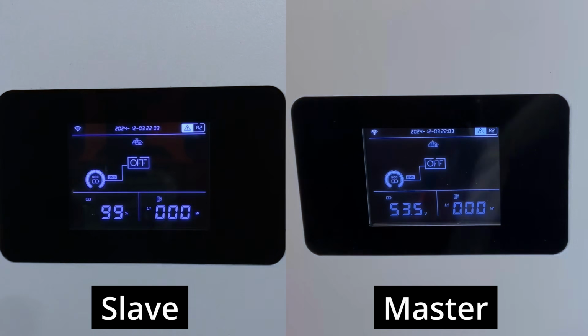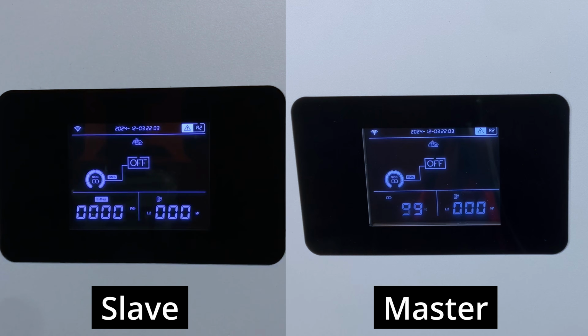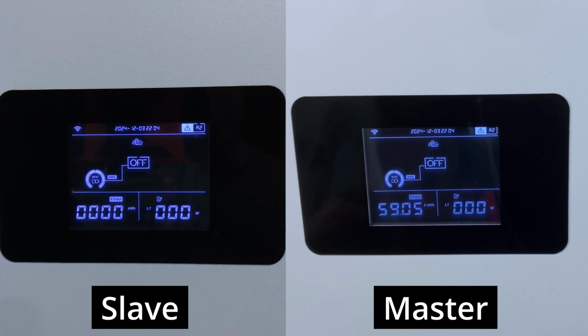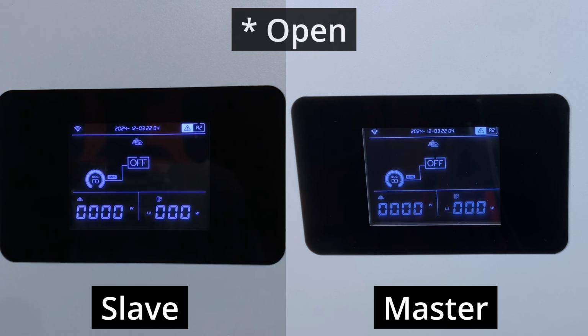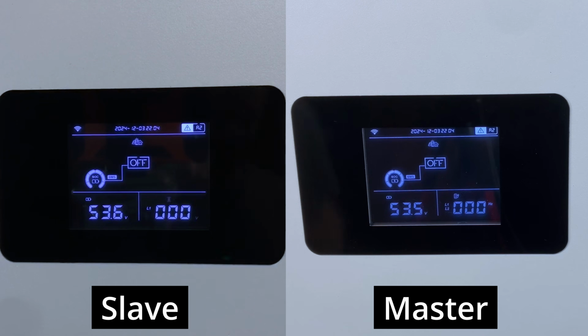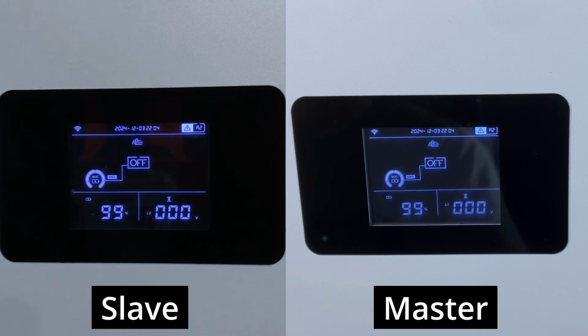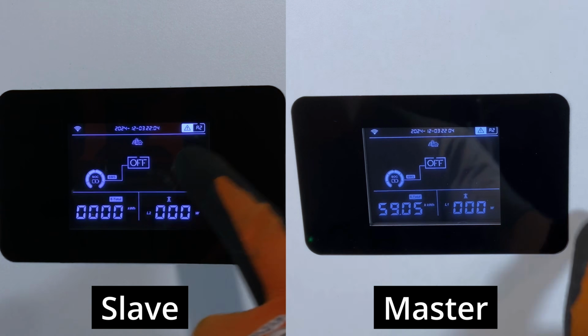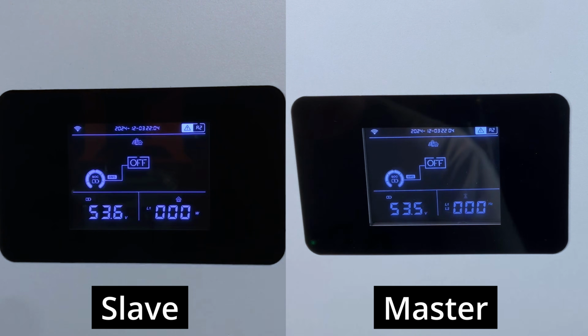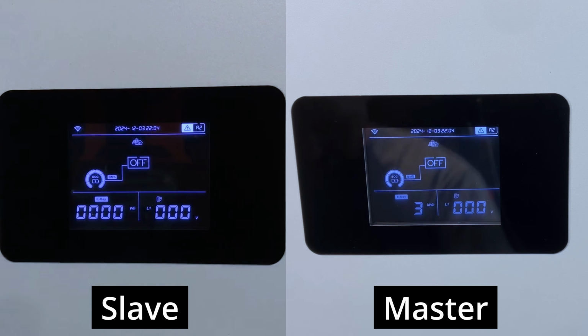I'm going to come over to our grid panel and turn on the grid supply. That hasn't done anything yet because we still have our breakers open on the inverters. So I'm going to turn on the AC input breakers on both, and we should see the A2 error goes away on both. I'll turn those on in 3, 2, 1.